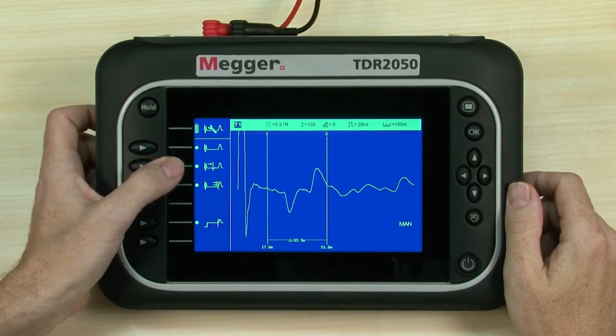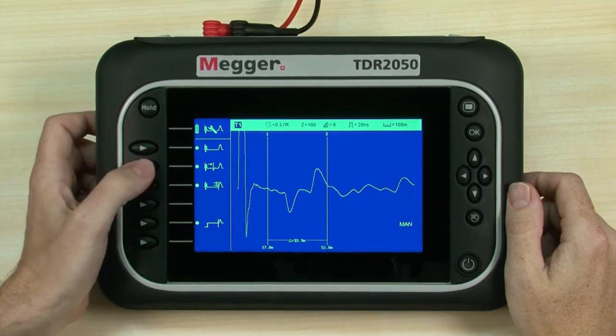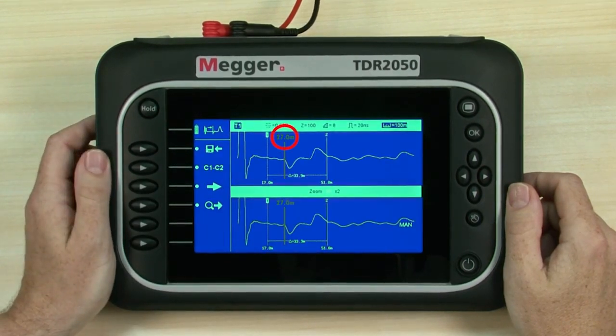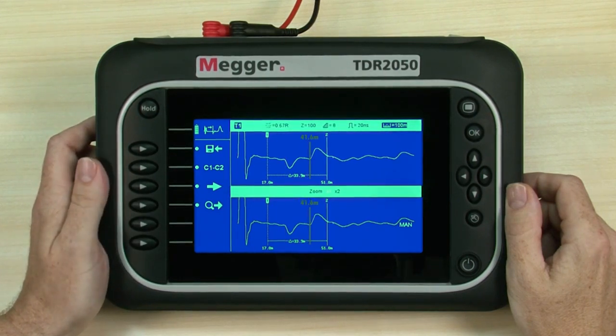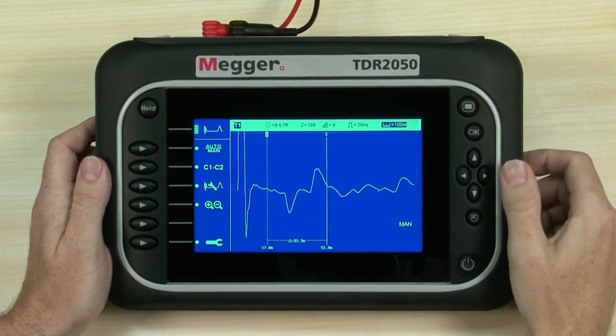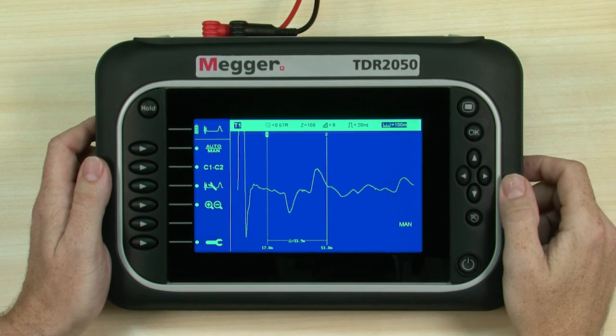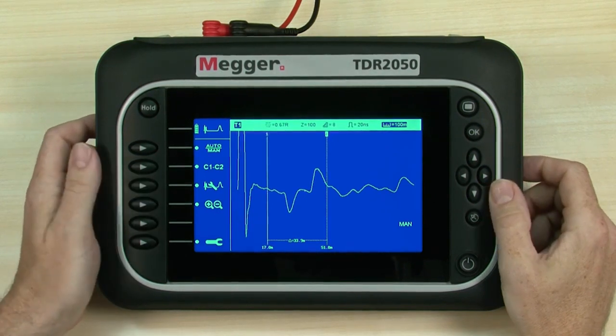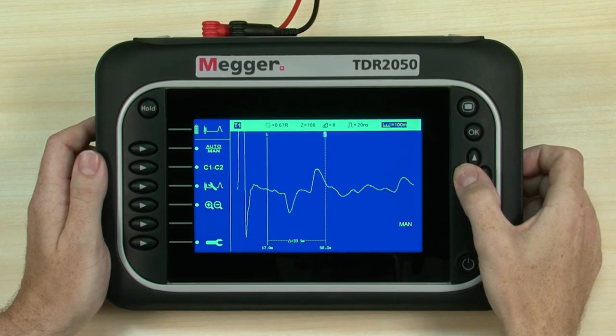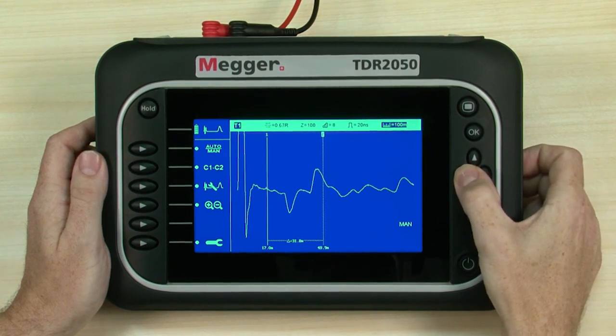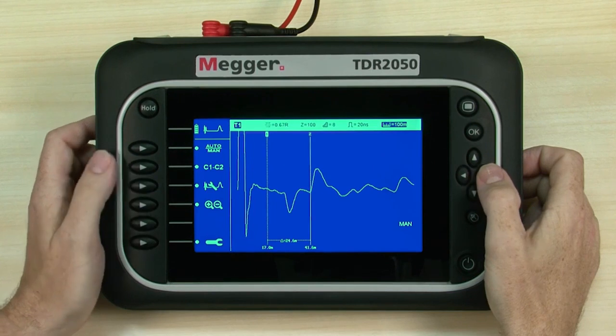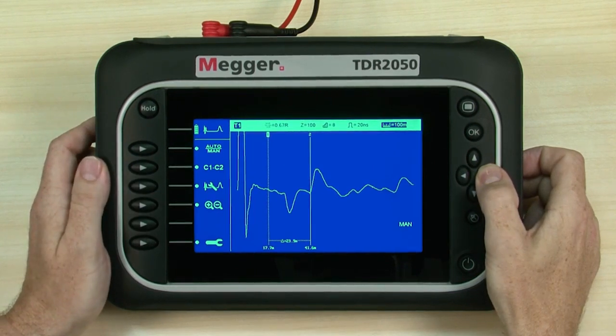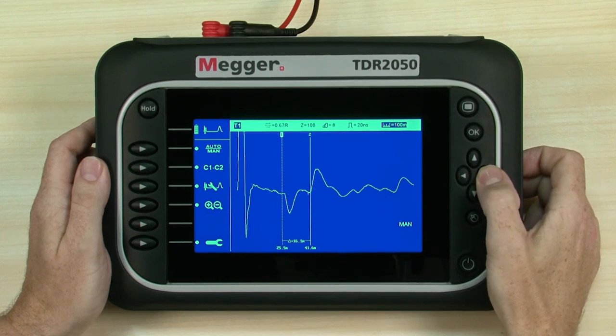Auto find allows us to jump directly to a detected event. An event has been detected and a marker placed at this point — the distance is shown at the top of the marker. Pressing the find next soft key automatically positions the cursor at the next event. Now let's return to the main screen where we can easily measure the distance between two events. TDR-2050 has two cursors which can be positioned at different events on the trace giving the distance. The C1-C2 soft key toggles the active cursor, which changes to a dotted line. Press the left and right navigation buttons to move the selected cursor; for extended distances, hold the navigation button down — its travel will accelerate after a second or two.